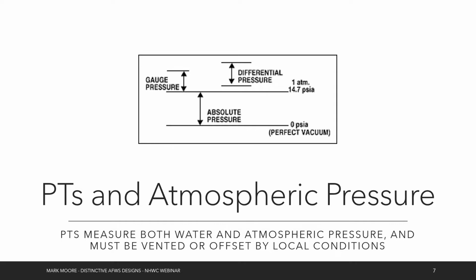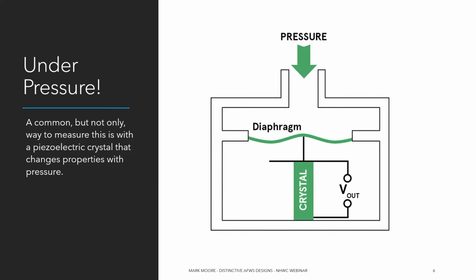So taking a quick step back and looking at this previous slide, with a pressure transducer, as I mentioned, that pressure is both water and atmospheric pressure. And so the most common way that you see this negated is by adding a vent line, which comes in on the other side of the diaphragm and helps cancel out that atmospheric pressure. And the reason that I'm being a little bit of a stickler about this is that vent tube, that vent line that goes behind the diaphragm and pushes back, it has to be kept clear. It has to be kept dry, and it has to be kept unbent, undamaged, and accessible. And that's why with a lot of pressure transducers, you see those vent tubes come out into some sort of desiccant box or a desiccant tube. And that keeps that vent tube nice and dry so you don't have condensation in it, which would block the pressure transducer's vent tube and cause it to get bad data.